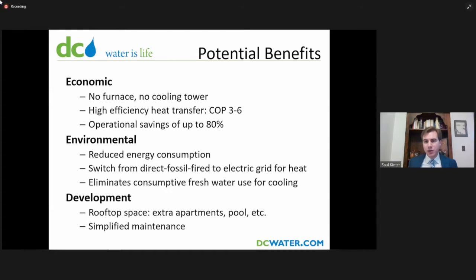In DC, we have a height restriction on buildings. The urban legend is that nothing can be taller than the Washington Monument, though actually the truth is far more complicated and bureaucratic. But essentially, DC is a city without skyscrapers. So rooftop space is particularly valuable, because the developer, if they want more square footage on a particular lot, cannot actually expand by adding more floors. So with the ability to move equipment off the roof, eliminate cooling towers or air handling units, and instead have equipment in the basement that's hooked up to the sewer, is quite a big financial benefit for a developer.